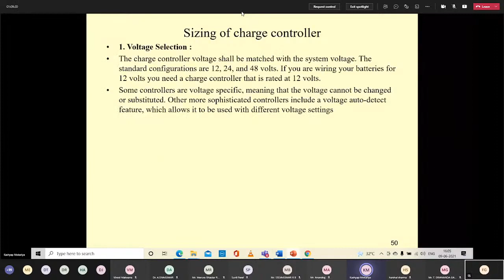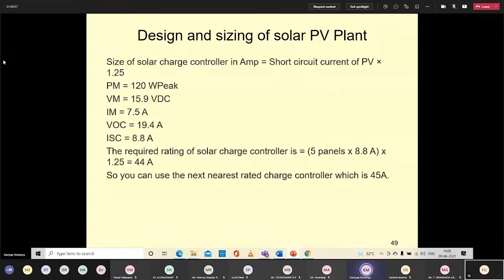This I have already gone through in nominal voltage sizing, so here I am just clarifying it. If you have 2 options, whether you want to go for the standard 1.25 specification or for an NEC specification, then what NEC says, to select a proper charge controller, you have to know the maximum output current that we can get from the data sheet that I have shown you. ISC, once you get it, you have to apply a safety factor of 1.25 times 1.25. Now, what was that 1.25? You will get some literature saying you go for a multiplication of 1.25, but I suggest you not go for 1.25 but go for 1.56.